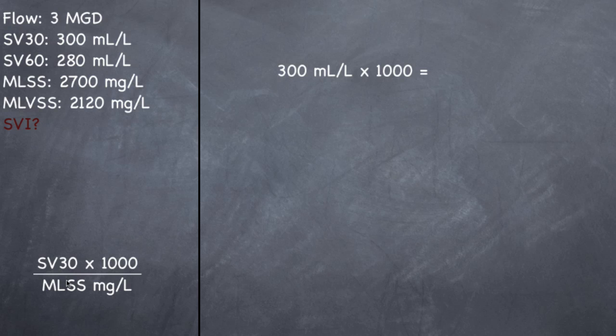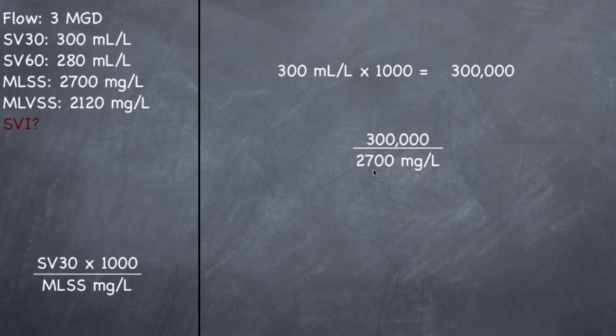So SV30 times 1000, our SV30 is 300 milliliters per liter times 1000 will give us 300,000. Now we divide that number by our mixed liquor suspended solids concentration. 300,000 divided by 2700 equals 111 milliliters per gram. It's kind of a unique form, milliliters per gram.